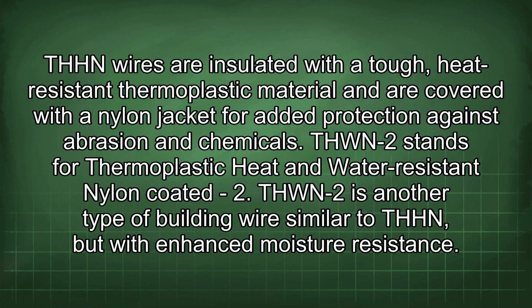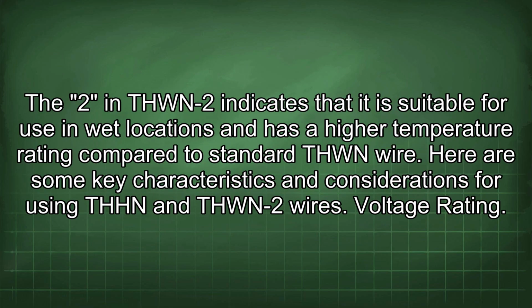THWN-2 stands for thermoplastic heat and water-resistant nylon coated 2. THWN-2 is another type of building wire similar to THHN, but with enhanced moisture resistance. The 2 in THWN-2 indicates that it is suitable for use in wet locations and has a higher temperature rating compared to standard THWN wire. Here are some key characteristics and considerations for using THHN and THWN-2 wires.